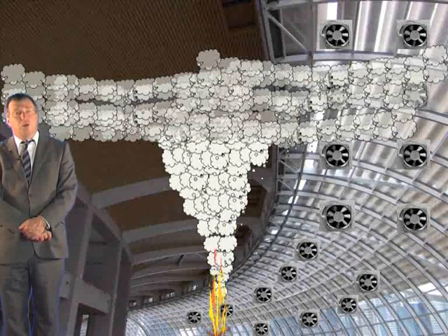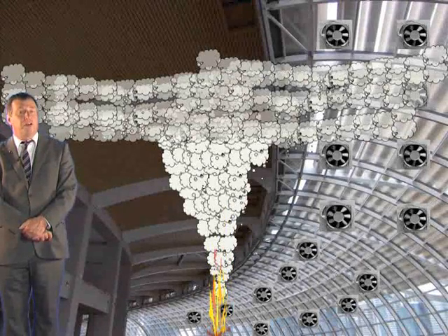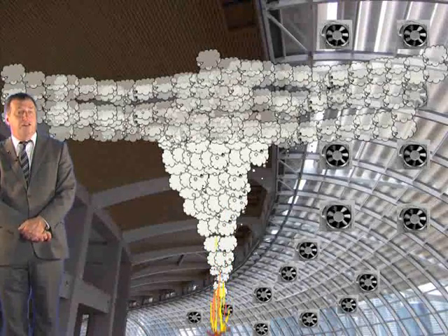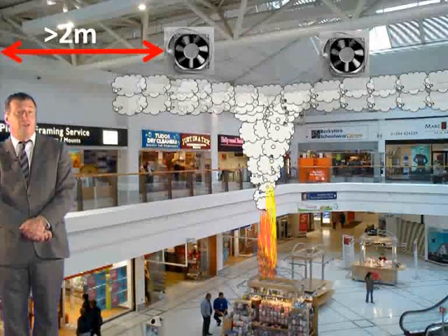There's no model for quantifying the effect that plug holing has on the amount of smoke that is exhausted via the ventilator, so the only practical way to deal with it is to ensure that plug holing does not happen. There are two basic models that are used to check whether or not plug holing is likely to occur, and they depend upon whether the ventilators are close to the edge of the reservoir or further away from the edge of the reservoir.